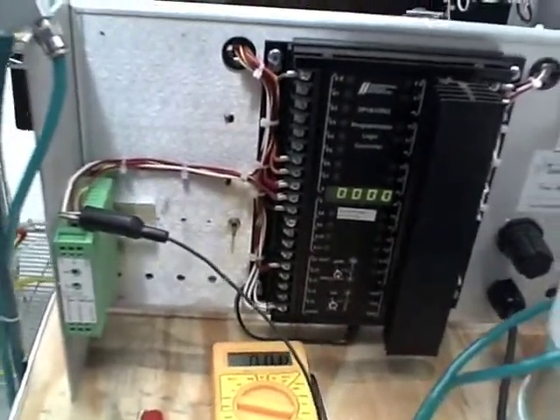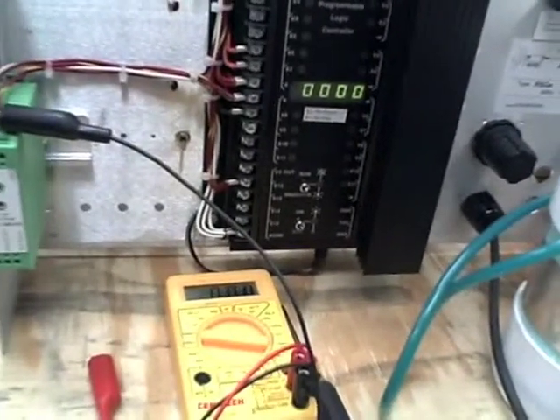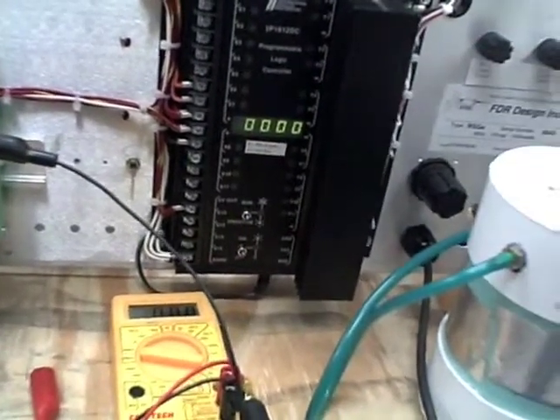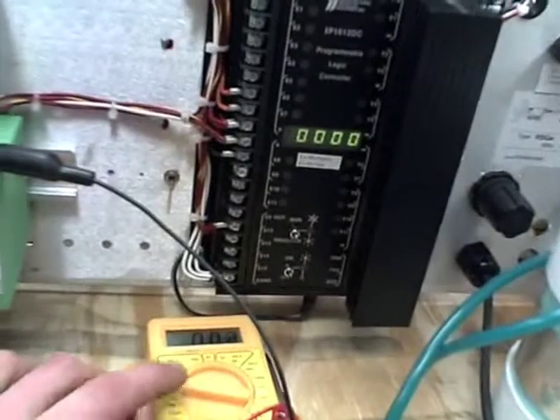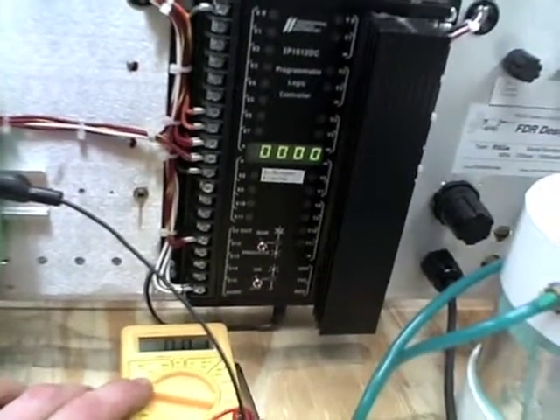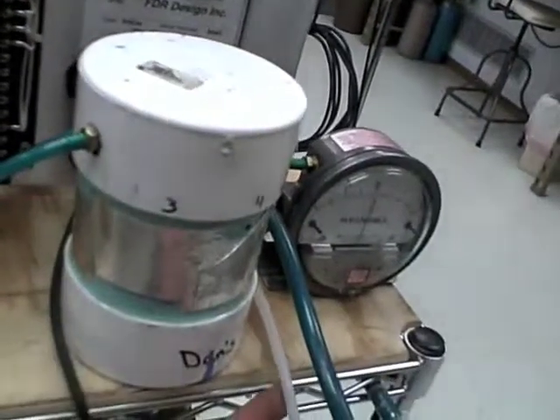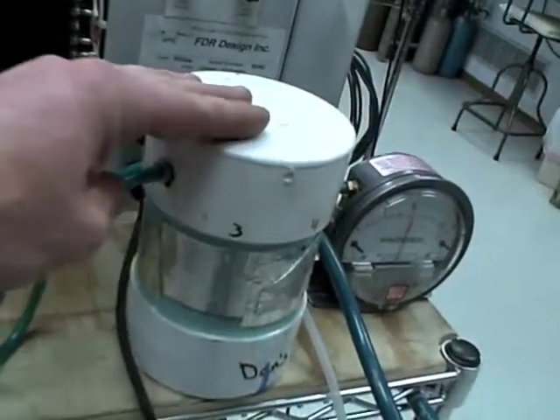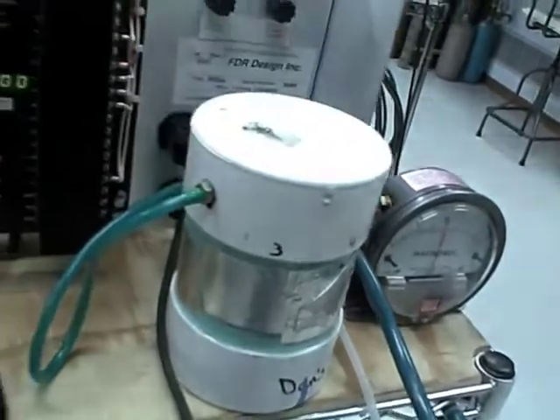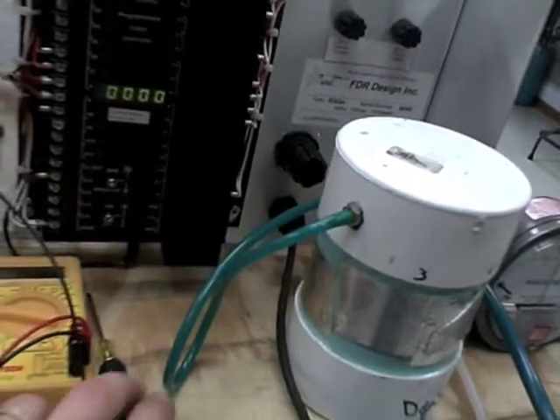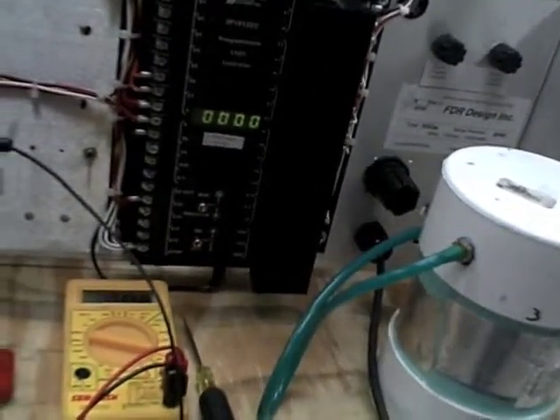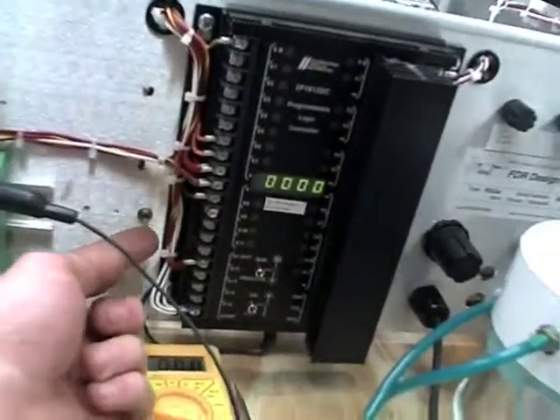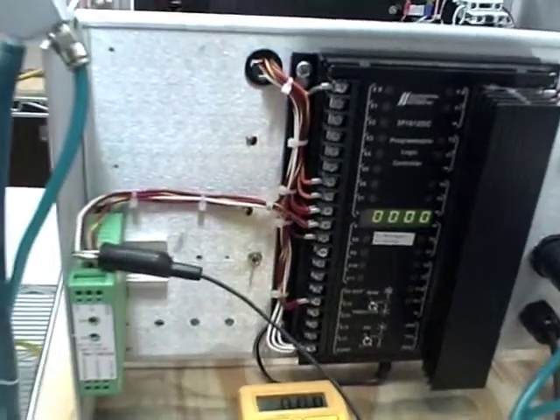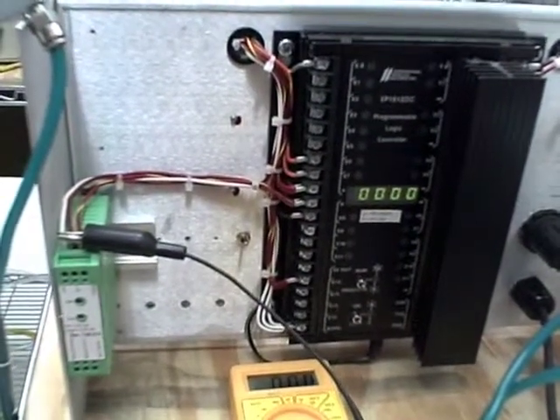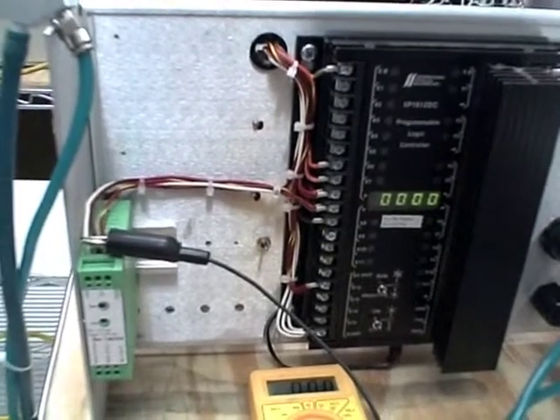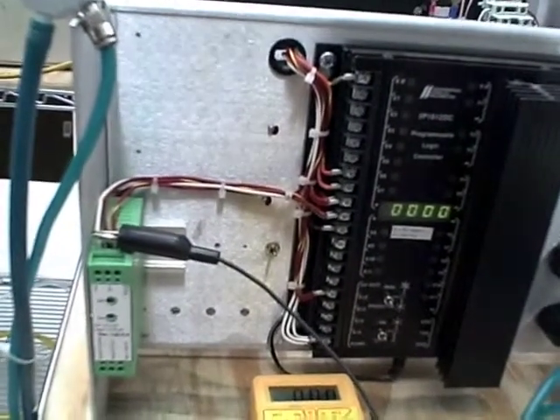Okay, now the next thing we're going to do is walk through the steps of calibration, and for that we're just going to need a voltmeter, and we're going to need gas hooked up to the machine, and I have that over here. We're also going to need this test jug with the magnehelic. We'll use that a little bit later on, and a screwdriver. So the first thing that we're going to do is put the sensor override switch up, because we don't want the machine to beep at the end of the cycle. We want it to keep running. So we'll put that up.